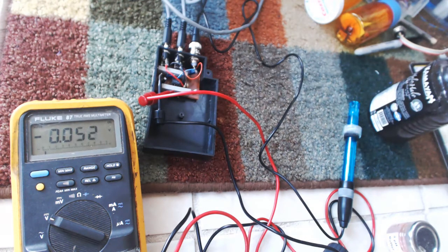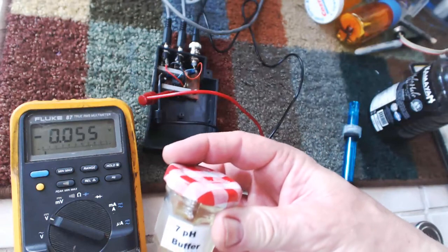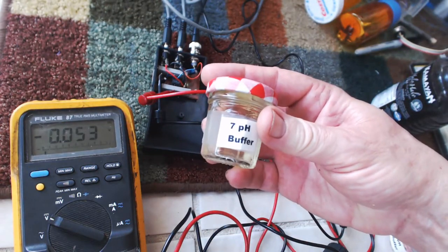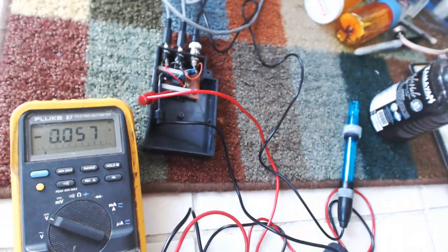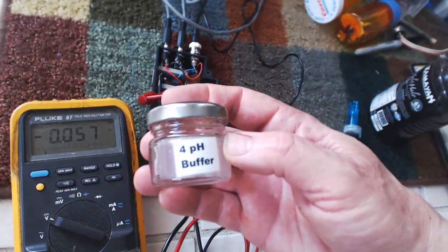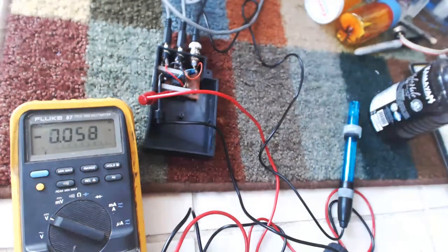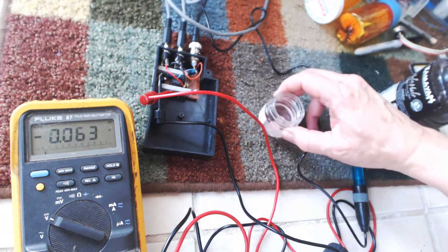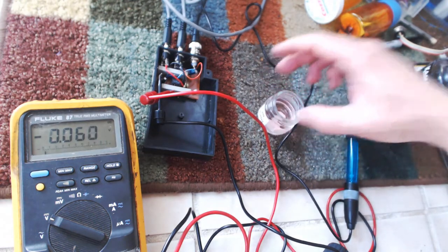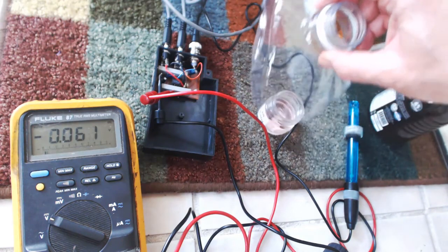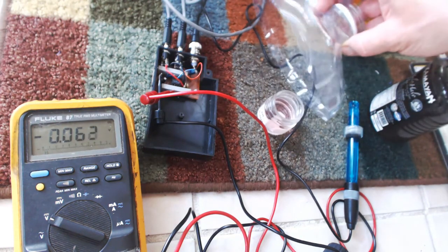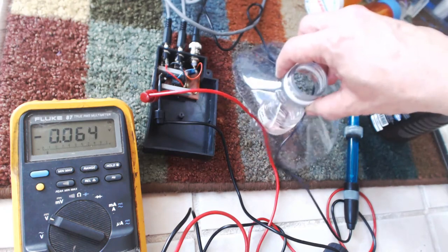Bear in mind here, of course, you'd probably want to actually go through this sequence twice if you're looking for a very accurate measurement. That means I'd go ahead and do the 4 solution after I do the 7. Then I'd come back and do the 7 again. Then I get it, make sure the 0 is correct for that one. Then I'd go ahead and go back and do the 4 pH solution again. That way I'd be sure my meter is as accurate as I possibly can make it. To speed the video up, I'm only going to do all this just once. I'll do the 7, then the 4, and then we'll do the test sample.